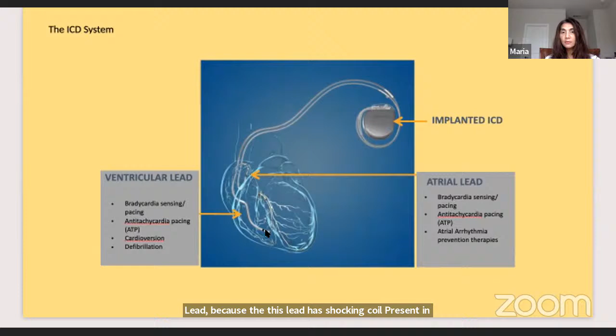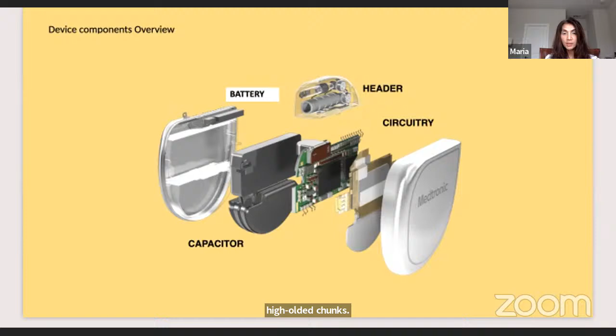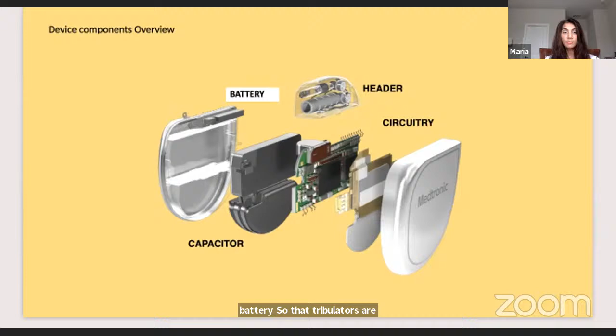The defibrillator differs from the pacemaker in its circuit and battery. It has a battery and circuitry just like the pacemaker, but also has a capacitor and transformer for generating high voltage shocks. The bulk of the device size is due to the capacitor and battery, so defibrillators are larger than pacemaker cans.